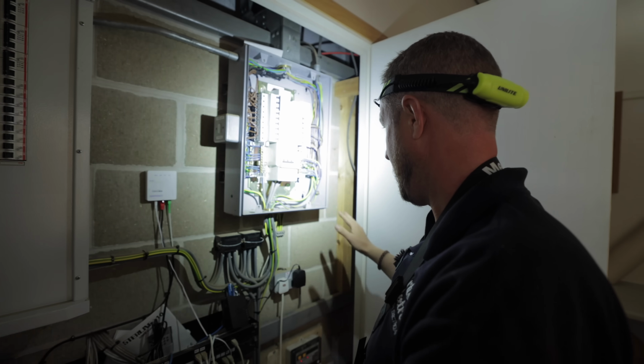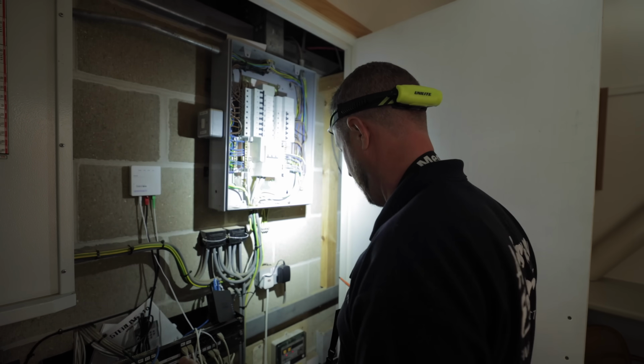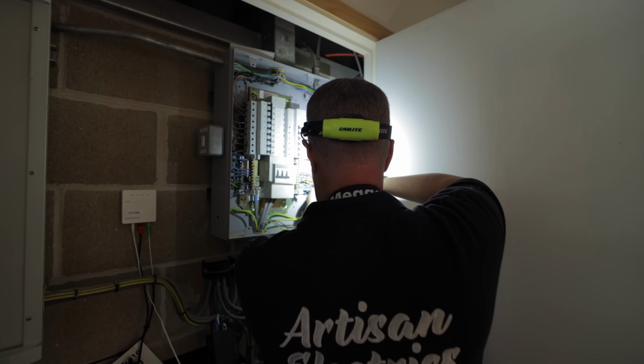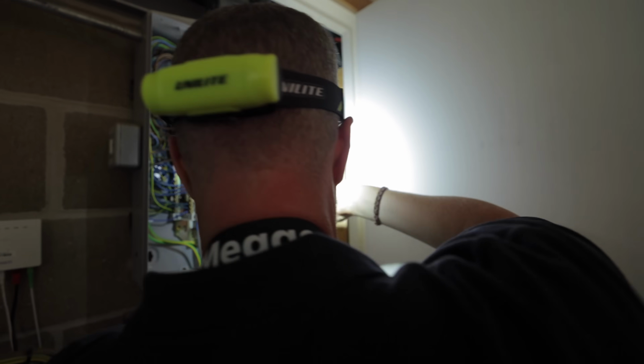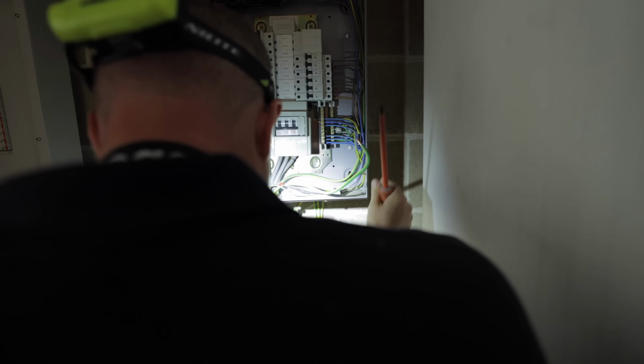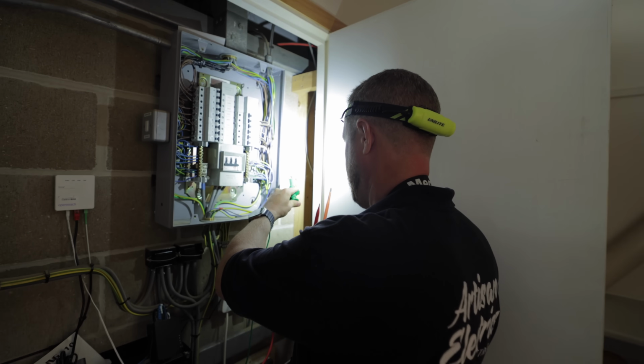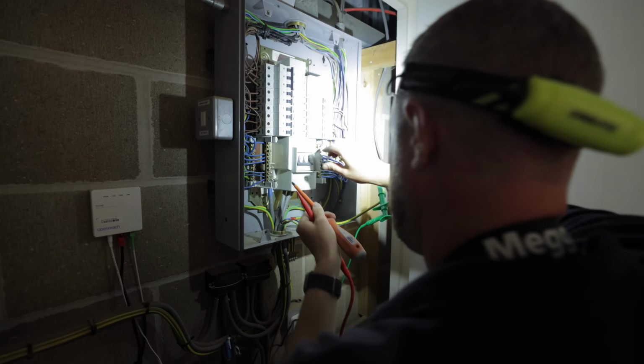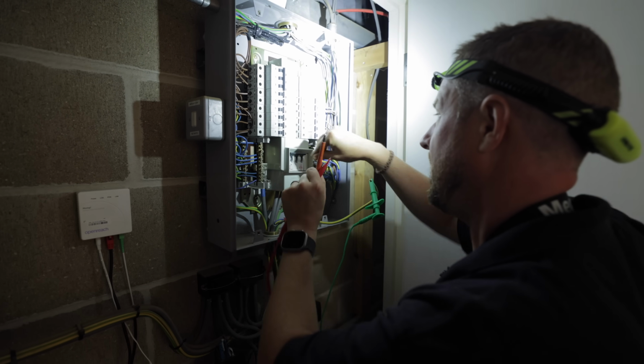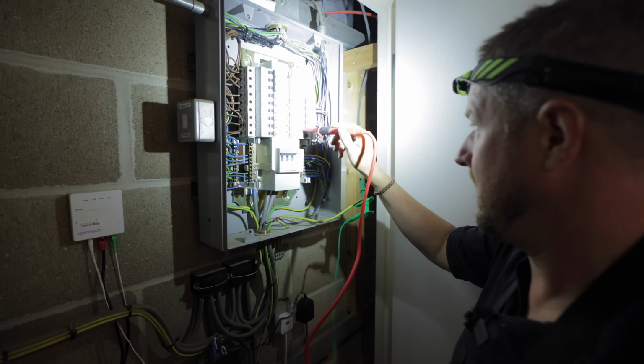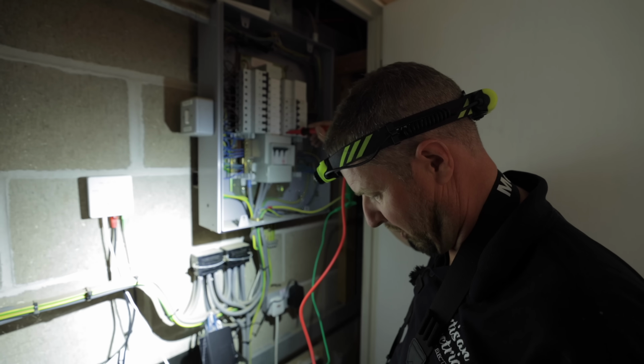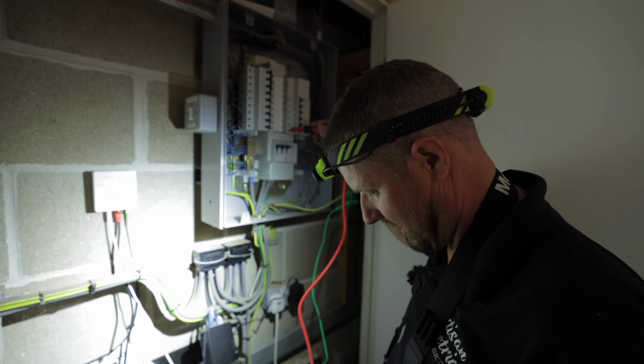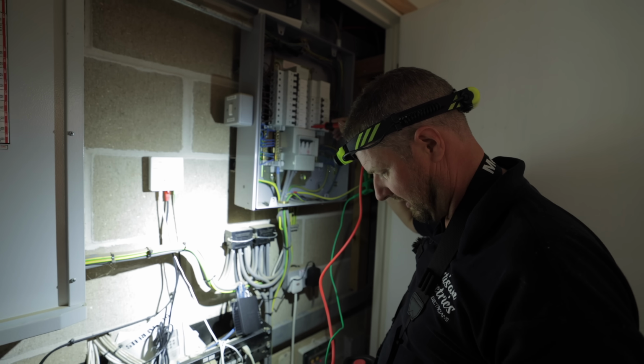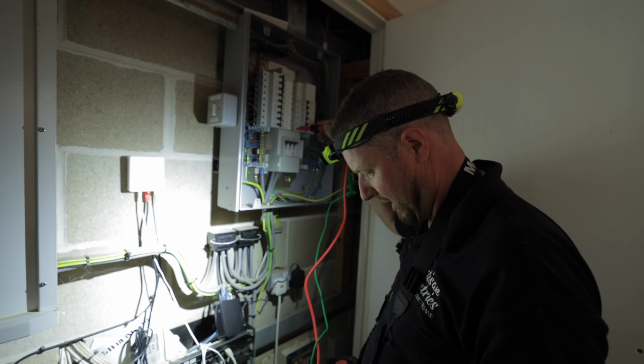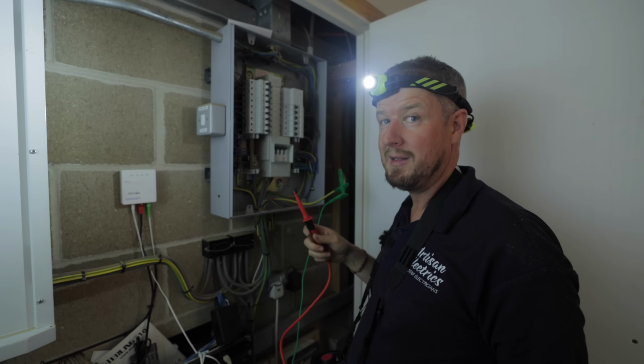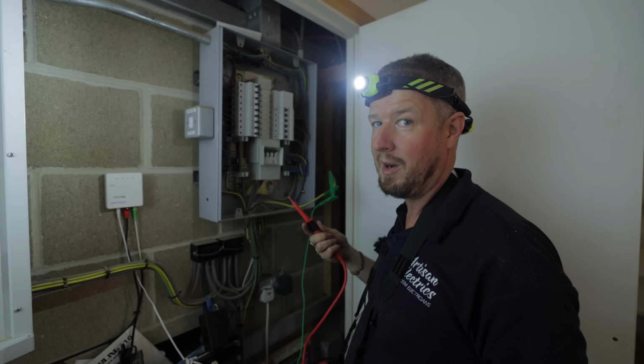Right, so now both our main isolators are off, all our boards are off, basically everything's off. We can safely disconnect our main earthing conductor here, like so. It's very simply a case of popping that on there. We can literally just turn our main switch on and then go on one of these. We've got 0.1 ohms for ZE and 2.36 kA for PEFC. Let me know in the comments if that's correct, and I'll tell you the correct answer in a bit.